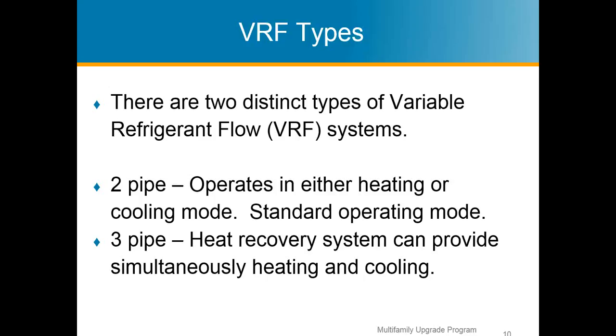Now the three-pipe is the heat recovery system, and this is where you find even more savings, referring to that last slide where I was showing the HVAC site energy savings. They were using these heat recovery type systems. So you're able to simultaneously heat and cool two different spaces with the one condensing unit. It's a very handy thing, and they basically share refrigerant and share load, taking heat out of one place that needs cooling and putting it into a zone that needs heating.